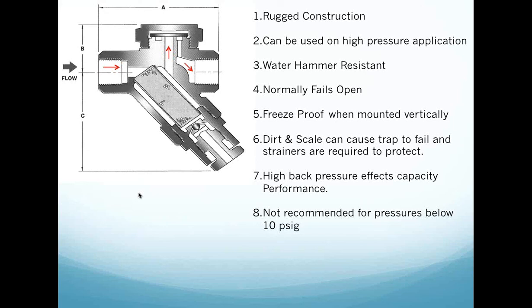They're very reliable. I will tell you this, though. It is machined surface, the disc and the seat, and you have to protect those with a strainer. And you see this particular trap with a built-in strainer. Those need to be maintained and blown down so that we keep dirt and scale away from these, because this thing cycles anywhere from 6 to 12, 15 times a minute. If it's machine gunning, then you could have dirt or scale built up between the disc and the seat, or you could have a trap that is just so worn that you can't hold the steam in the space, and so it's called machine gunning, where the disc is just cycling, and you will literally hear it. You don't need ultrasonic listening devices or a stethoscope. You can literally hear the disc from outside, even with earplugs and a hard hat on, and be able to hear this thing in a failure mode.